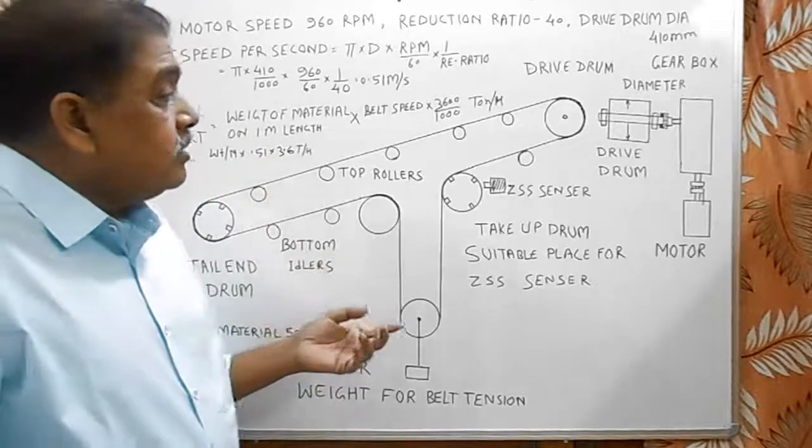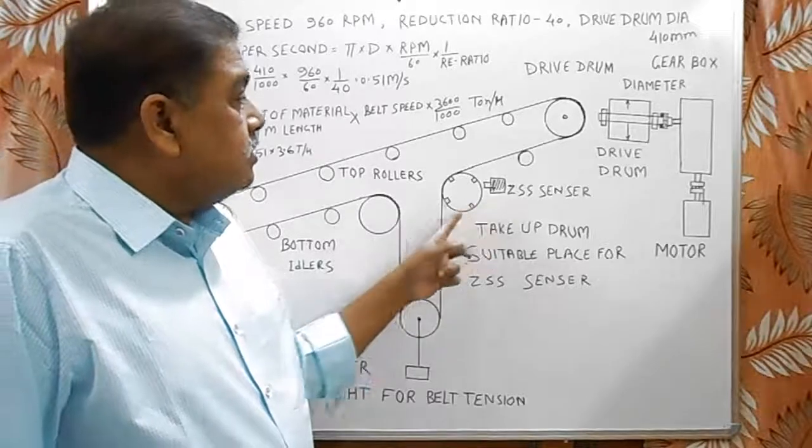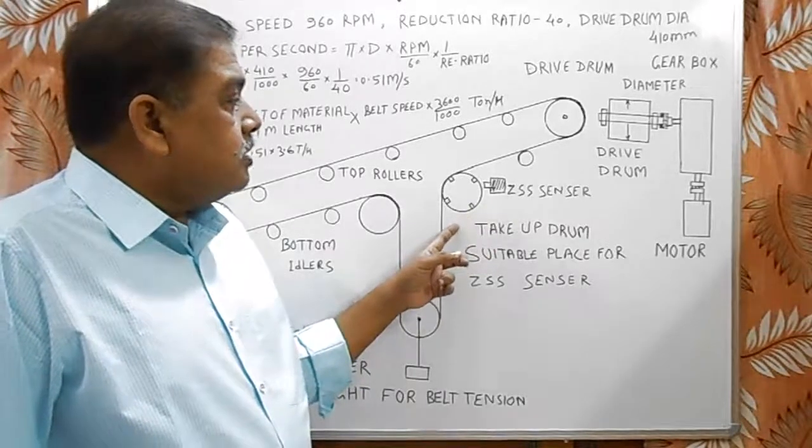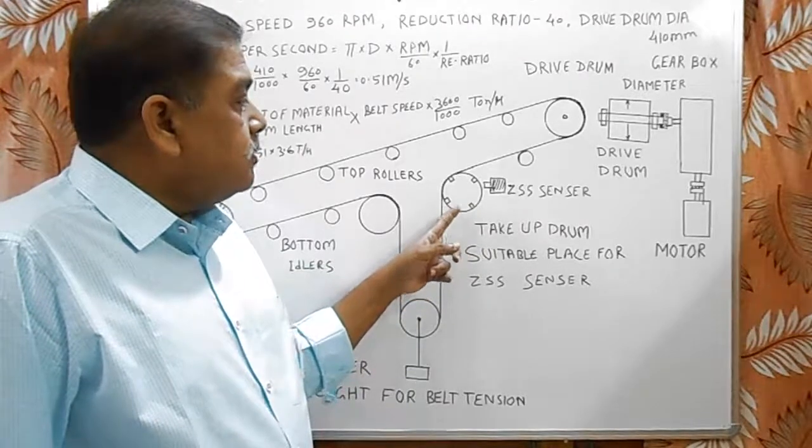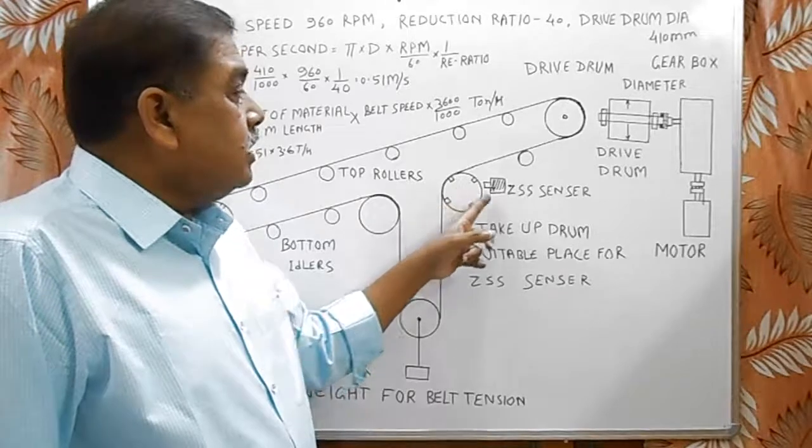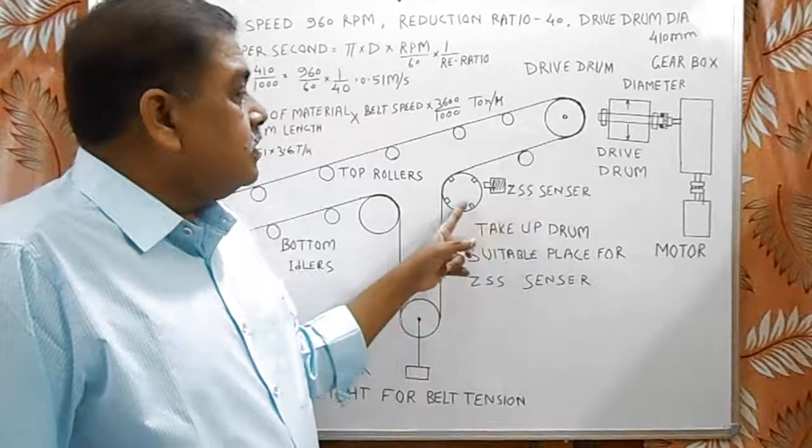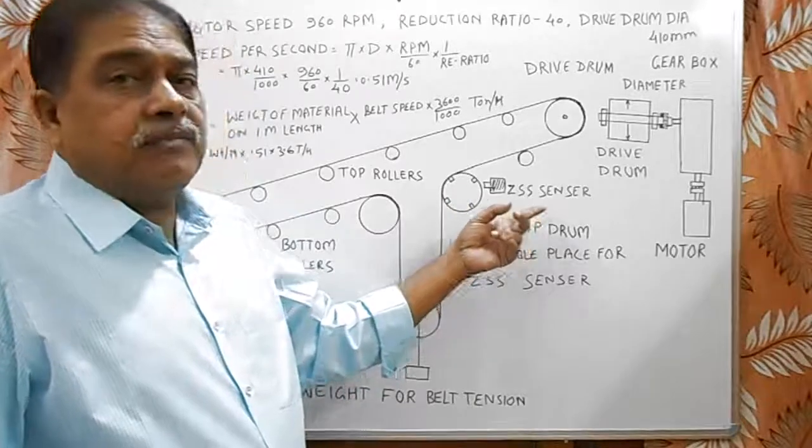In this, for the safety of belt, we use ZSS. The take-up pulley is the best place for fitting ZSS sensor. Here, we put 4 magnetic pieces welded on the drum. And this is ZSS sensor. From here, the wire goes to ZSS controller. And from there, the wire goes to the main interlocking circuit of belt conveyor control circuit.